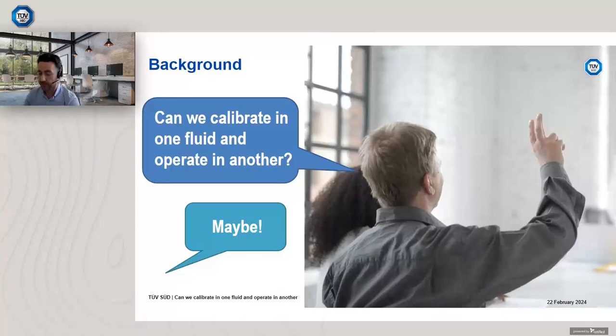Most flow facilities will utilise a different oil, potentially being just simply a mineral oil. The viscosity and density might be a close match, but they obviously won't be identical. And natural gas, the composition will vary. Or you might be sending it to a facility that calibrates with nitrogen, for example. So straight away, you could be already calibrating in one fluid and operating in another. However, I'm aware that's not really what folk are referring to.